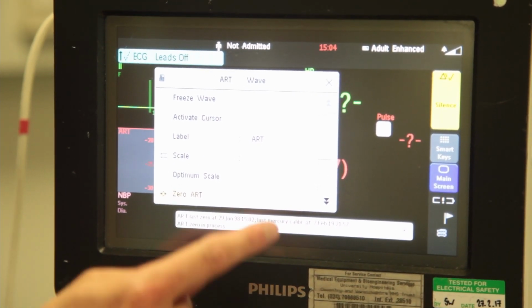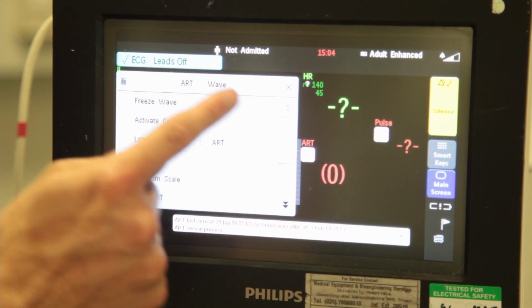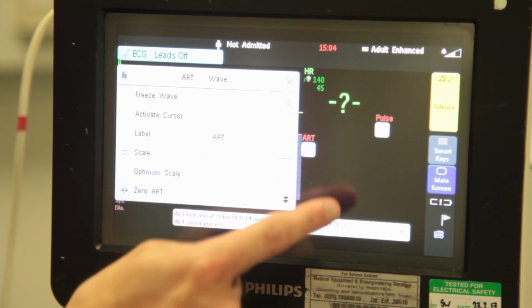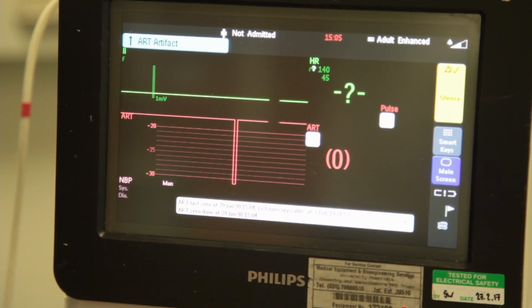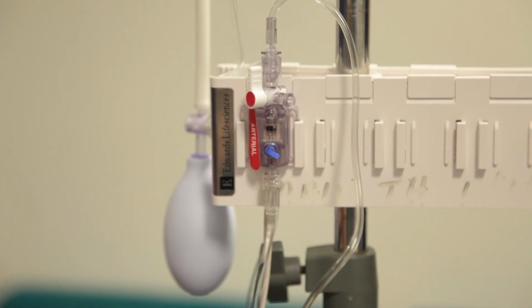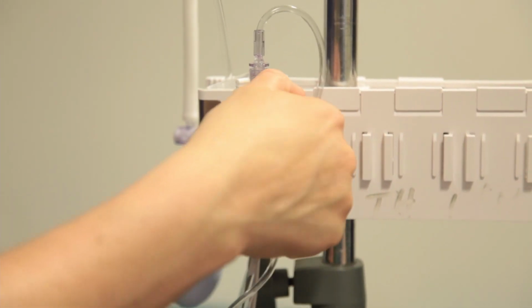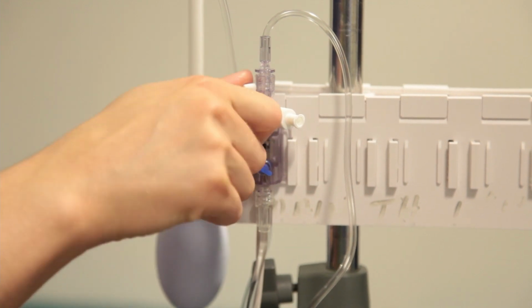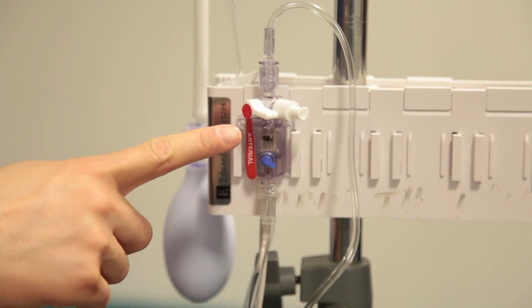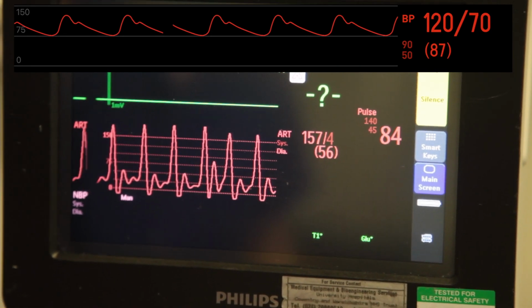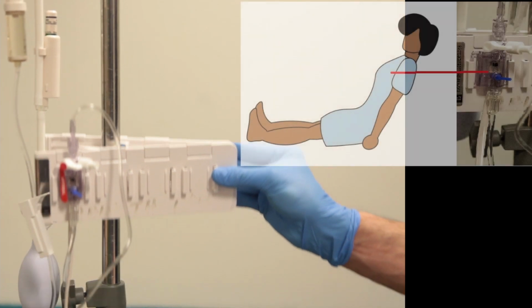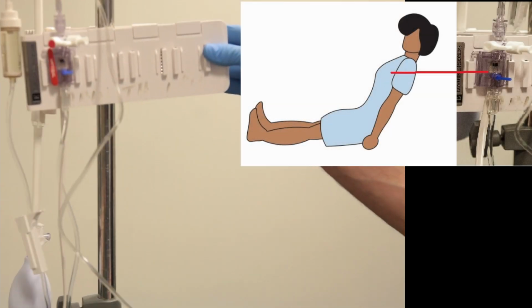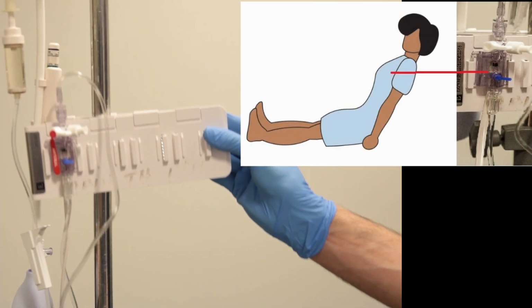When the red number reads 0, the monitor will beep and a small message will appear at the bottom. Reattach the bung and turn the arm back to face the port. The system is now zeroed and an arterial waveform trace with blood pressure values should be visible on the monitor. Be sure to place the transducer holder at the level of the patient's heart for accurate values.